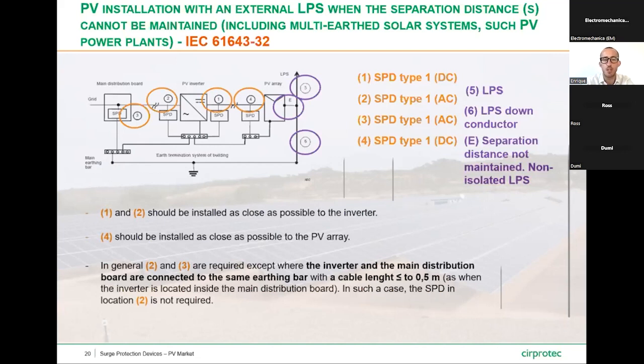The SPD in the location 1 and in the location 2 should be installed as close as possible to the inverter. Then the SPD in the location 4, to assure the proper level of protection in front of sources, should be installed as close as possible to the PV array.